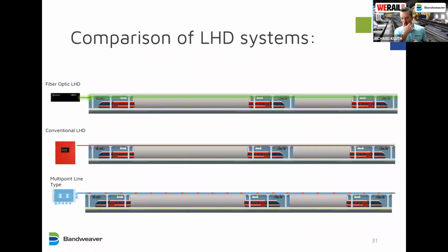So to highlight how they work, I thought we'd go through a tunnel, examples of fire in a tunnel, comparing different linear heat detection systems and how they compare. So we've got 3 tunnels here. The top one, the fiber optic linear heat detection system. The middle one, a conventional copper-based linear heat detection system.